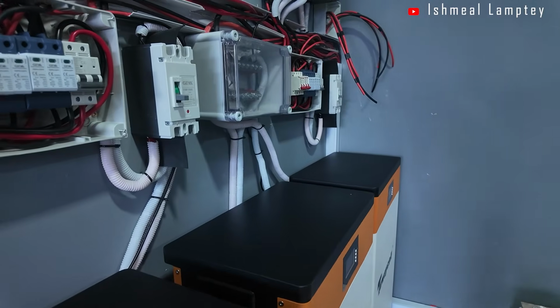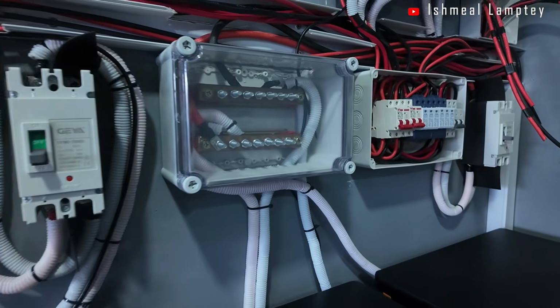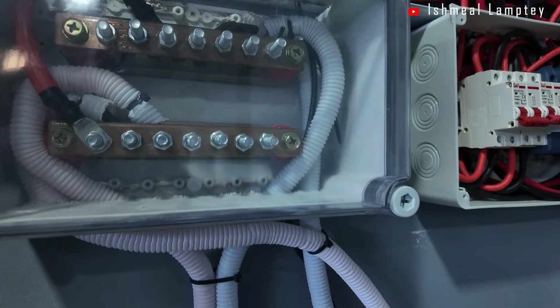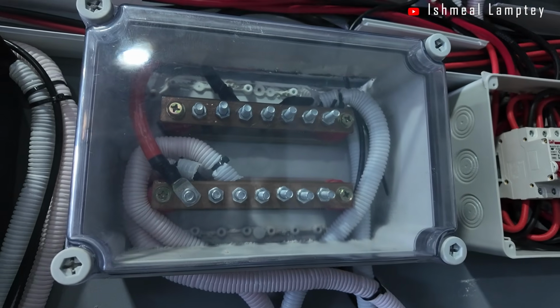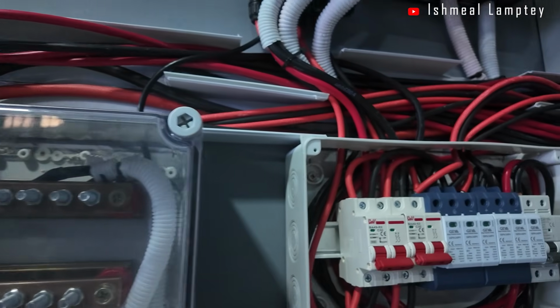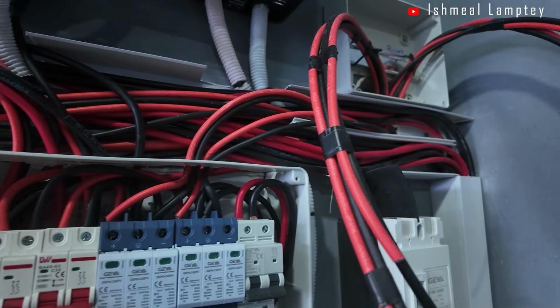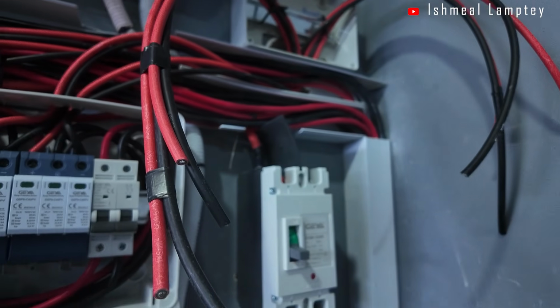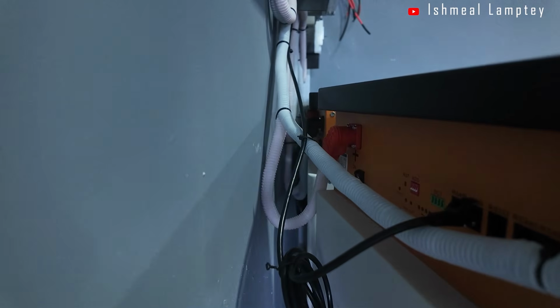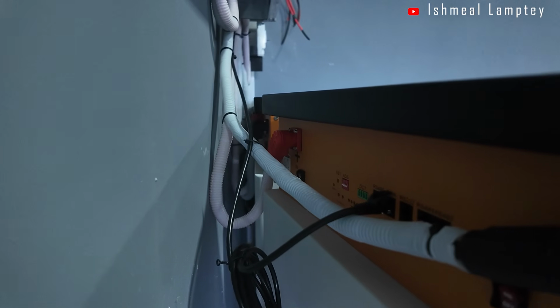For the battery, since we were paralleling 2 batteries together to serve one floor, there was a need to use a bus bar, which is in the middle. We did the configuration there - positive to one line, negative to the other - with the other battery also connecting in. So we paralleled the batteries, and as part of that, the batteries had a BMS system where you could connect both so they communicate.